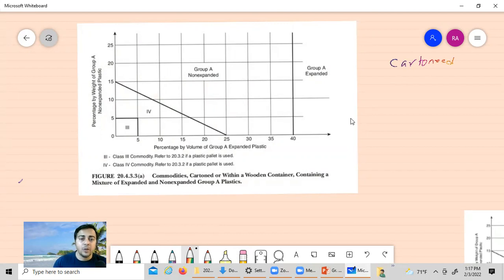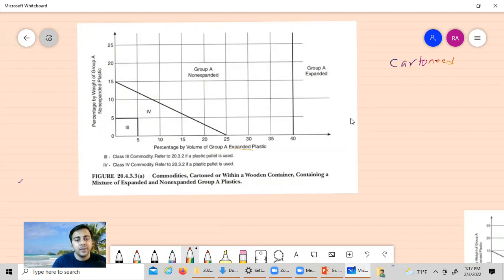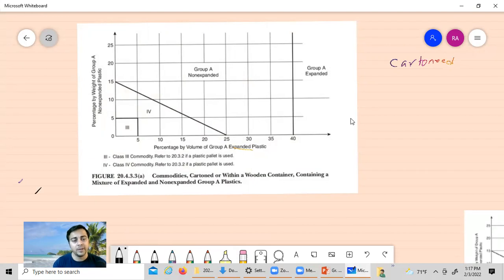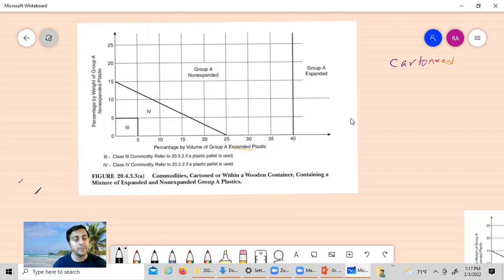On the x-axis they show the percentage by volume of Group A expanded plastic, and on the y-axis it is the percentage by weight of Group A non-expanded plastic. So it is expanded versus non-expanded plastic — expanded measured by volume and non-expanded measured by weight.